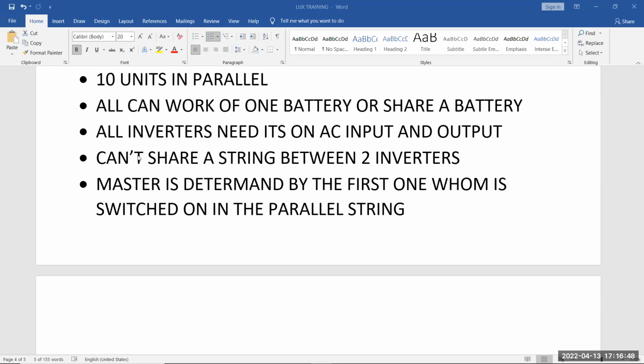Strings: each inverter has to have its own PV input. What I mean by that is, if you have one string on the roof between 2 inverters, you can put that one string only on one inverter and it will charge, but you can't take that same string and give the power to one inverter and bridge the string to the other inverter so that both inverters run off the same power from one string. You have to have independent strings on your inverters, if I can put it like that.